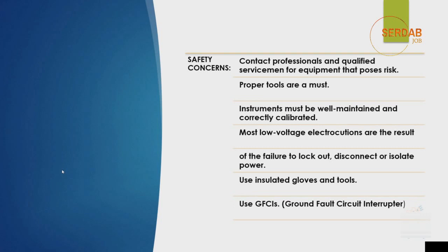The next step is instruments must be well maintained and correctly calibrated. Some instruments need professional calibration by an expert in the field. So if you are dealing with a chemical equipment board, you must make sure that someone from the same field is there with you to help you know the right adjustments and the right values for the calibration in order for this board to work correctly.